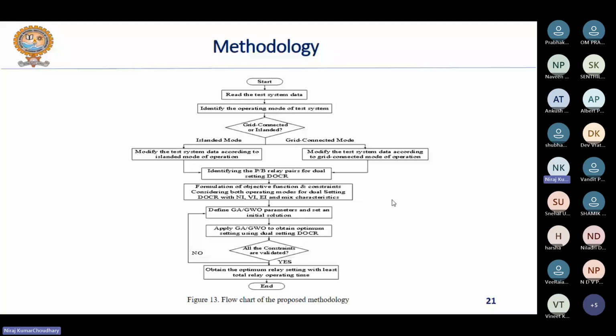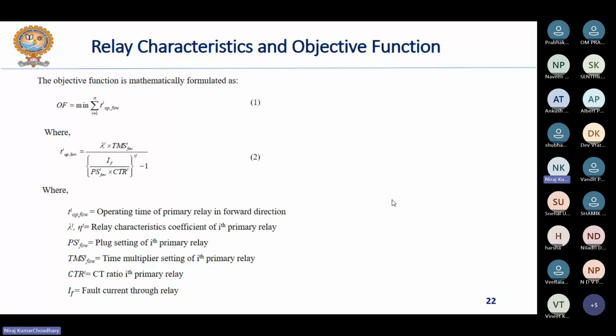So here, this is the expression of the objective function. In some literature, you will find that they have only considered the time of operation of the primary relay. Here, forward is mentioned because I have used a dual setting overcurrent relay, right? That's why T_OP,FOW is your operating time of the primary relay in the forward direction for fault current. I have shown you the forward and reverse direction of fault current in the previous slide. And this is your IDMT characteristics of the relay, standard IDMT characteristics.